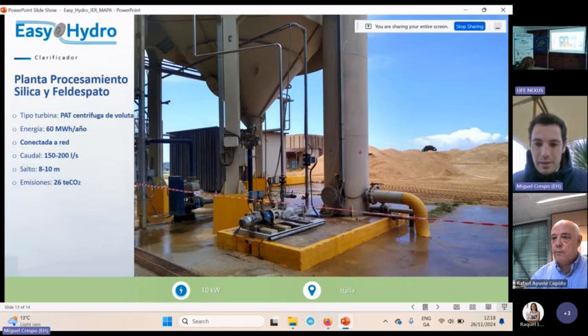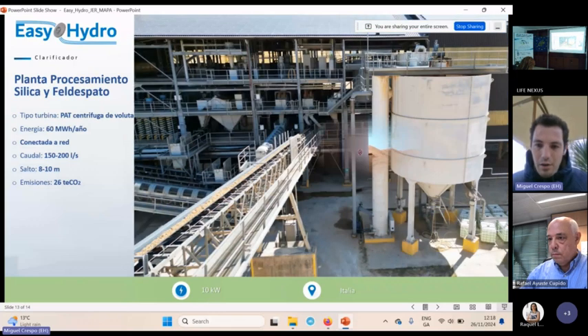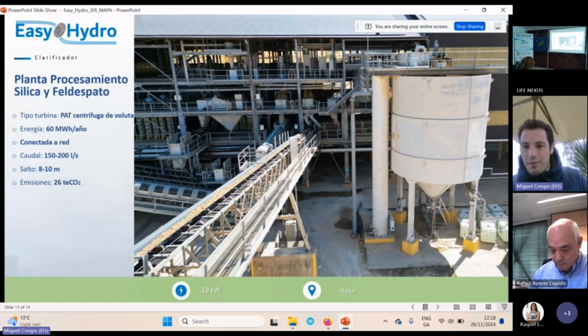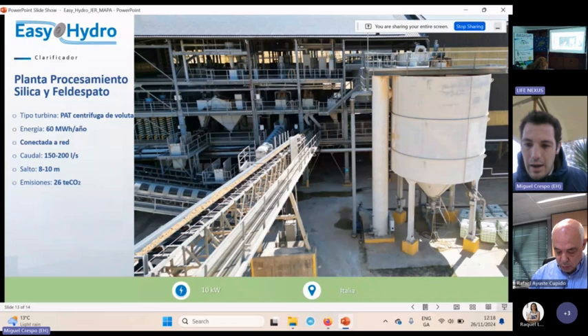On the other hand, this is a large flow, low head kind of system. Here you can see this is in a mineral processing plant in Italy. This is at the very last stage of the water treatment process. We have a clarifier of about 10 meters height and a flow being treated between 150 and 200 liters per second. To have an idea of the scale, here you have the height of the clarifier. On the left, you have the overflow pipe.